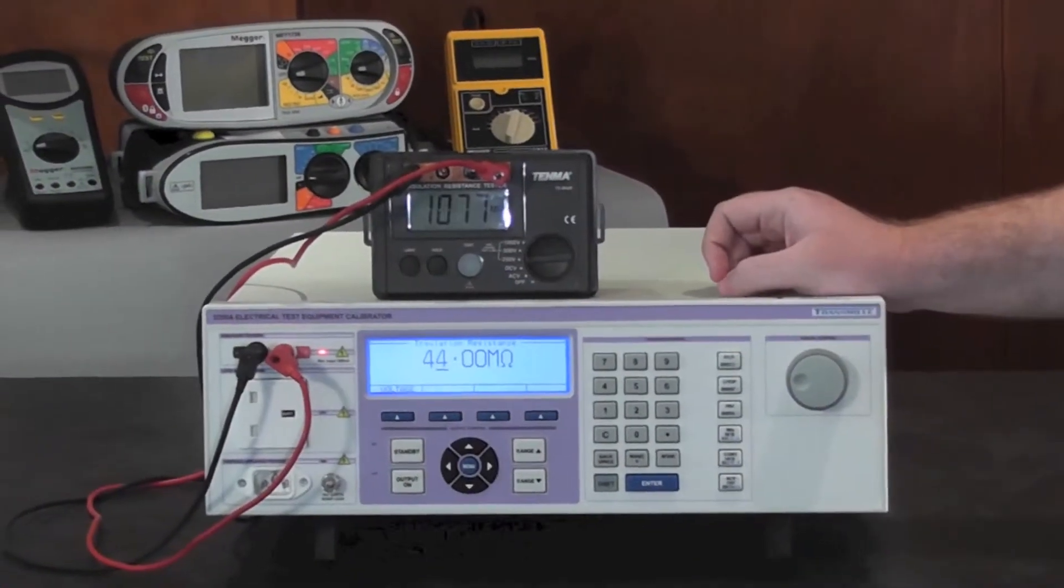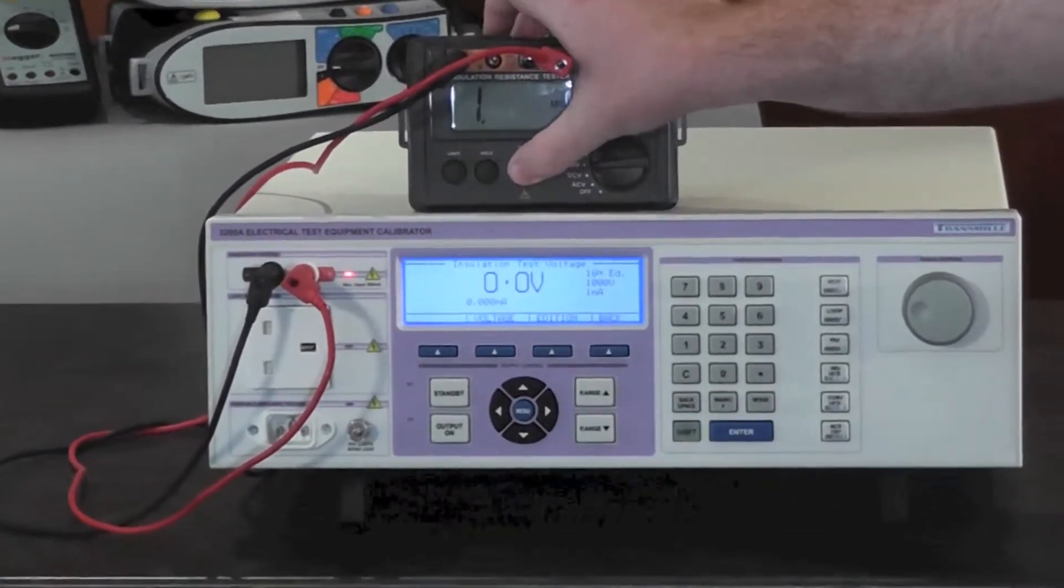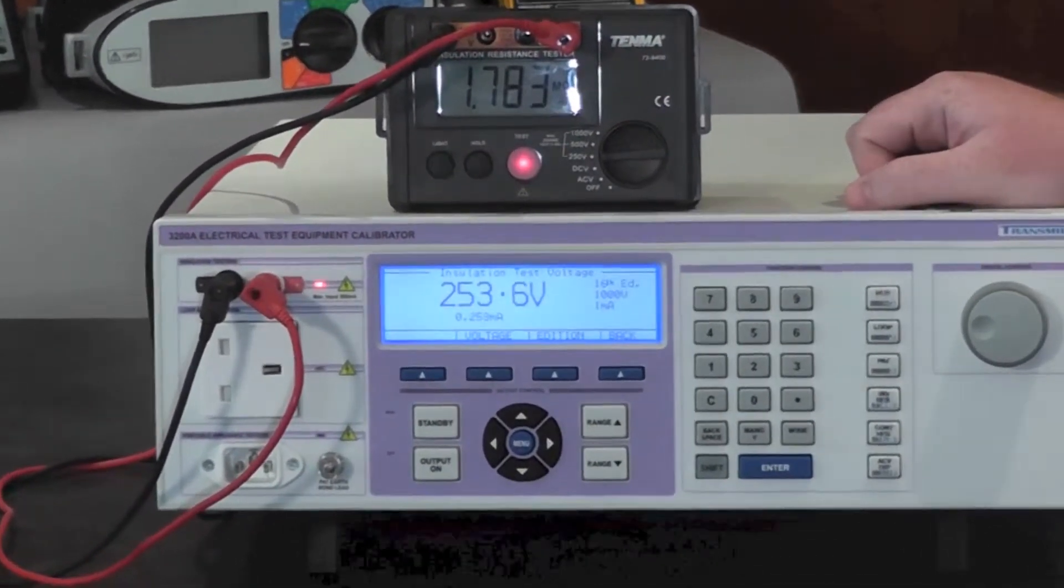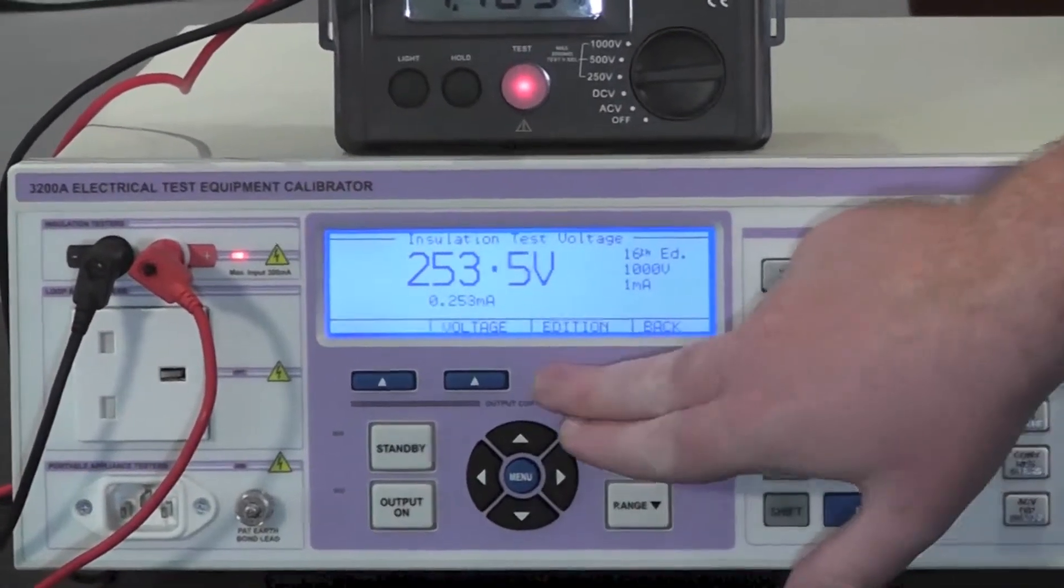The 3200A also has the ability to measure the test voltage. This can be tested to both 16th edition regulations as well as 17th.